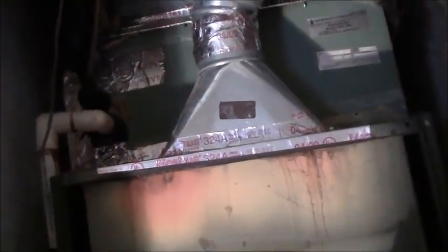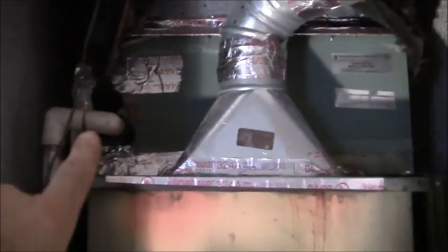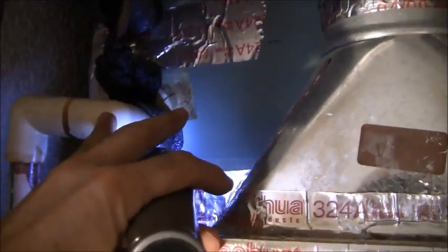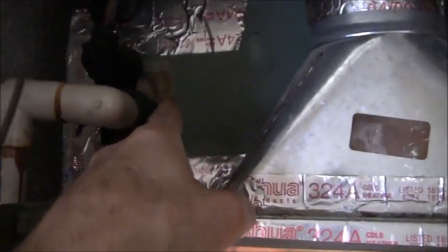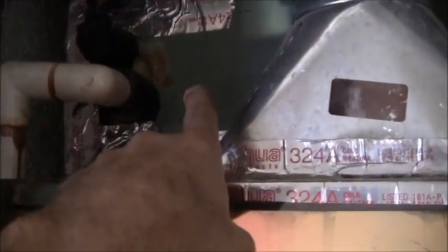Okay, so now looking at the system, you can see that the AC coil is right here, right above the furnace. And this here is the condensate drain line. They did not put a trap in when they built it, and they just used PVC piping. What I ended up doing was taking a saw and cutting this PVC pipe right there, and then using the shop vac and sucking out both ways. I put the hose going up this way so it sucked out from the evaporator drain pan here, which collects the water.